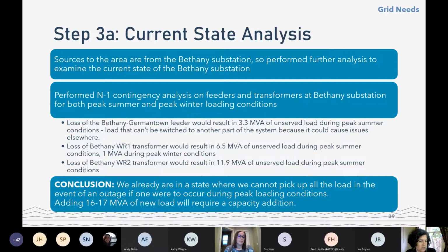The sources to the area were from the Bethany substation, so we performed further analysis, running N-1 contingency analysis on feeders and transformers for both peak summer and peak winter. We concluded that we could not pick up all the load in the event of an outage during peak loading conditions, so we needed a capacity addition.